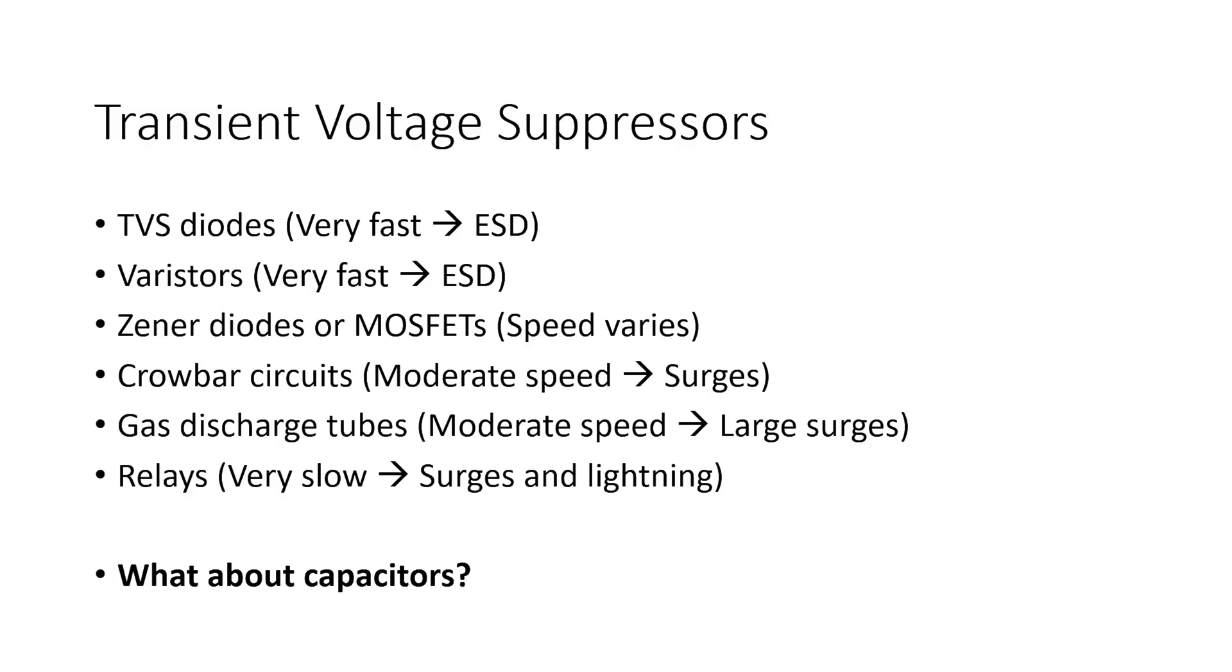If we look at the different options, we've got several in this list. Obviously, TVS diodes, there's also varistors, both of those are suitable for ESD suppression. There's also Zener diodes or MOSFETs. There's also crowbar circuits, they have moderate speed, they're essentially meant to shunt surges and possibly faster pulses of over voltage. You have gas discharge tubes meant to withstand much larger surges. And you can even use relays, specifically voltage sensing relays. Those are very slow, more meant for slow phenomena like surges and lightning.